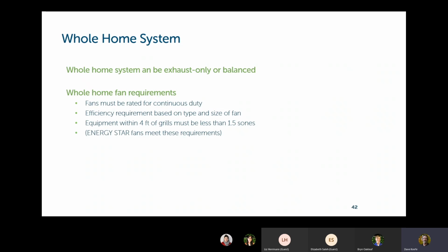The fans must be rated for continuous duty. There are some efficiency requirements based on the type and size of the fan. In other words, they have to be able to move a certain amount of air using a certain amount of electricity. Equipment within 4 feet of grills, so this would be something like your typical bathroom exhaust fan, must be less than 1.5 sones, so it's got to be reasonably quiet. And just a note there that if you buy a fan that has the Energy Star label, it meets those requirements.